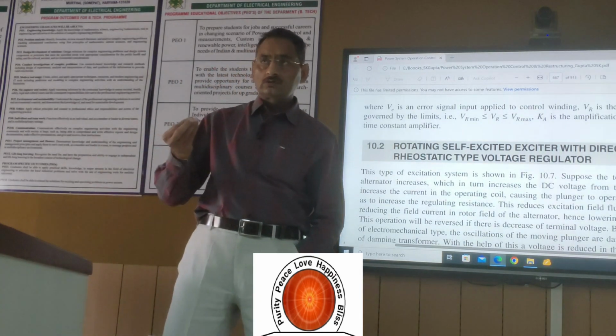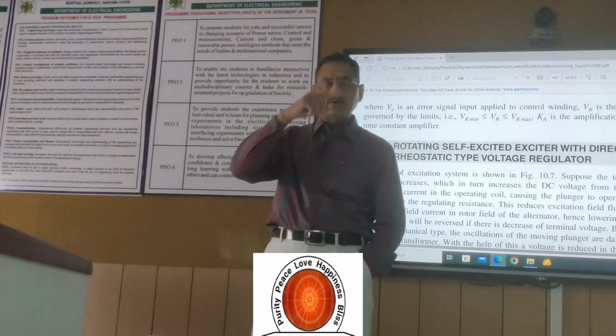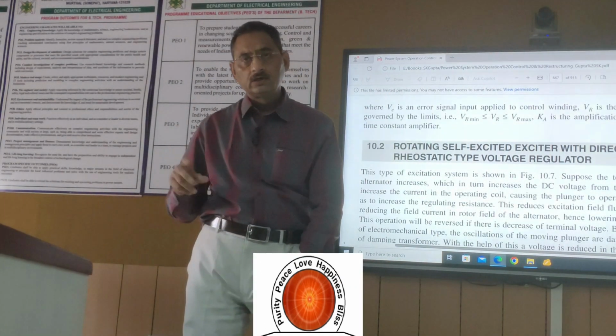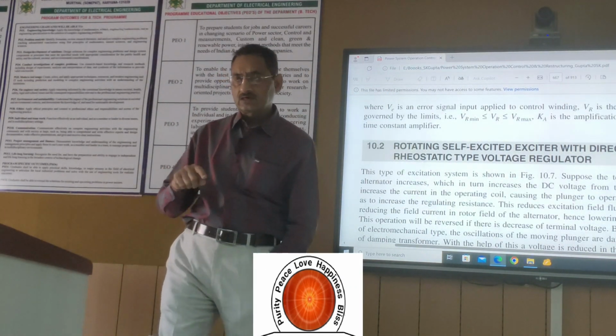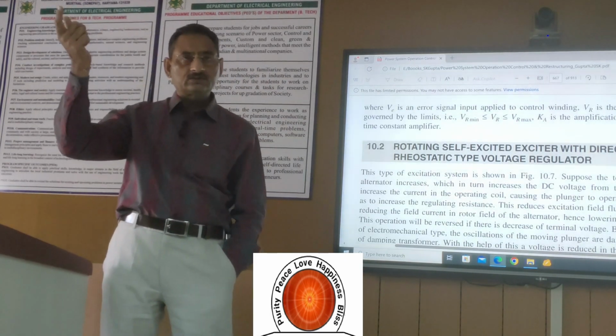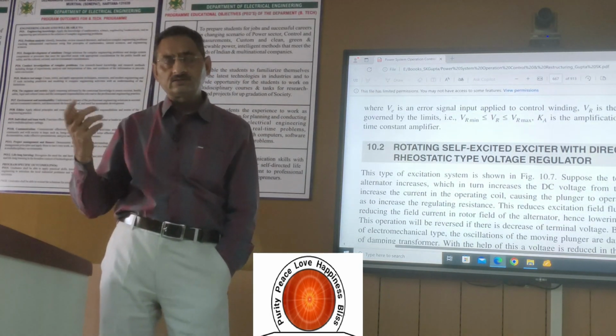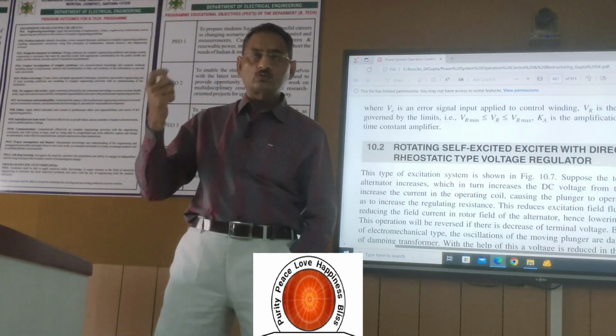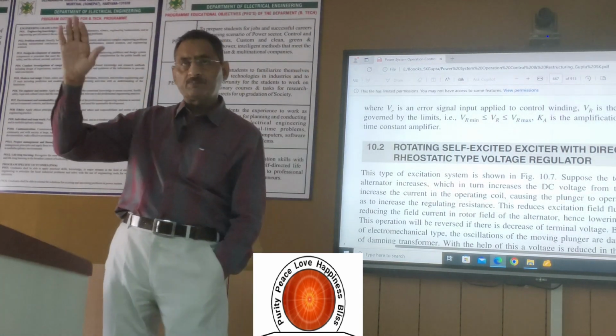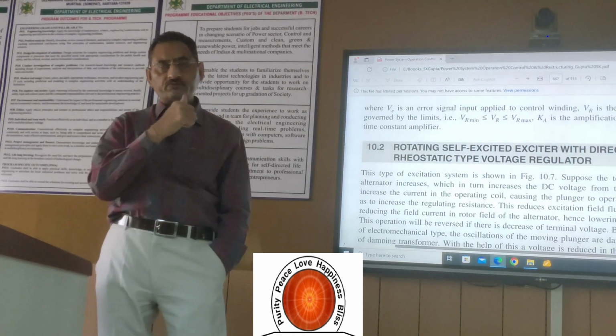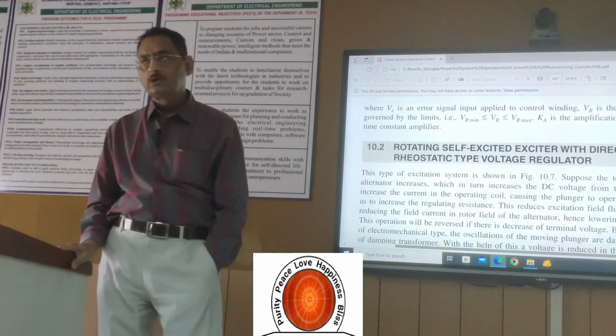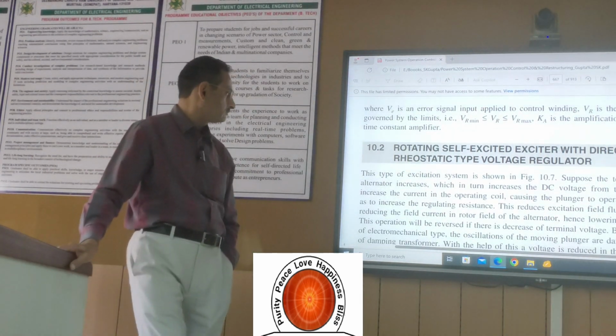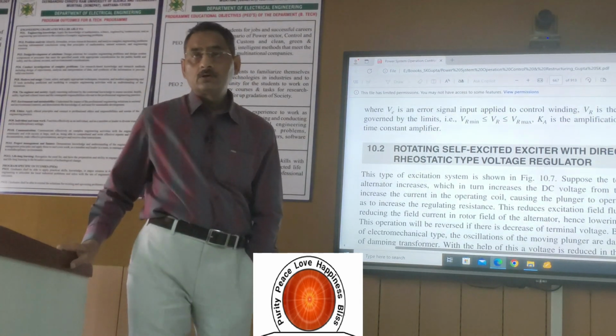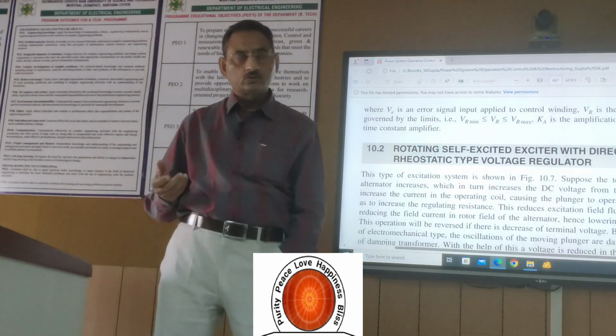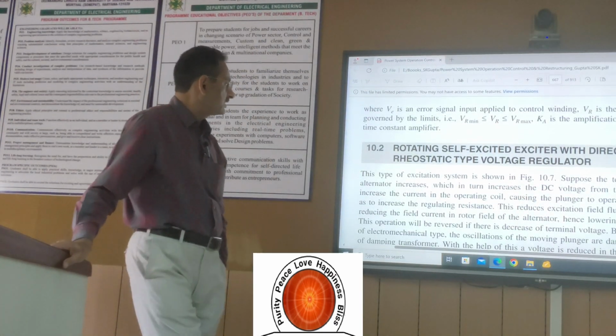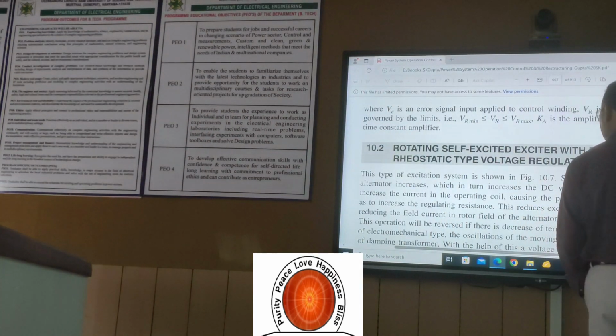Means the rheostat, the resistance of the field winding of the DC generator, is changed directly by taking the feedback from the AC generator. The terminal voltage of the main generator, whether it is up or down, according to that the rheostat of the field winding of the DC generator, that is the exciter, is varied. So it is the directly acting and rotating type. The exciter is rotating, so its name is rotating self-excited exciter direct acting rheostat type voltage regulator.